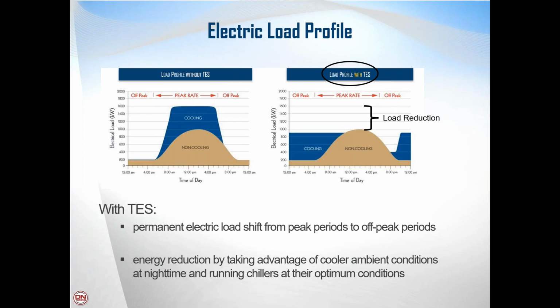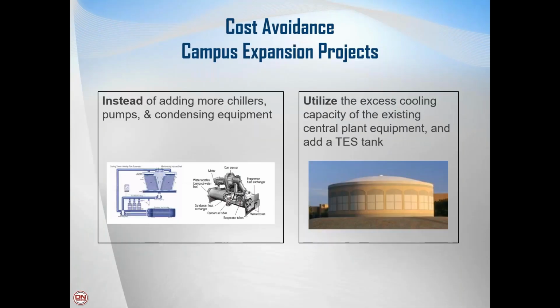And in addition to that, there is a consumption reduction for that campus. So if they're producing the cold water at nighttime and storing it in that tank, they're actually running their chilled water system when it's cooler ambient conditions outside. And that's typically when the chillers will run more efficiently, condensing at a lower ambient condition outside. So that reduces the kWh consumed to produce all those gallons of cold water. So there's a twofold benefit when you're utilizing chilled water thermal storage on both the kW demand side of the equation and kWh consumption side of the equation.